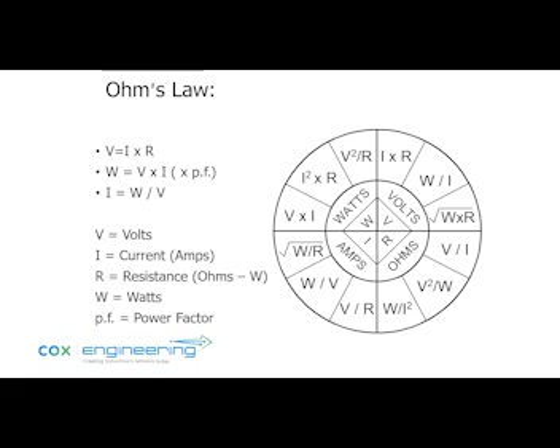And the deal basically is that if you know any 2 of those, you could calculate the third. So the way that we normally do it in a critical facility, and here's some examples. Let's start with a hair dryer. If it's a 1500 watt hair dryer and the nominal voltage is 120 volts, you take the watts divided by the volts, and that gives you the current, which is 12.5 amps at 120 volts AC.